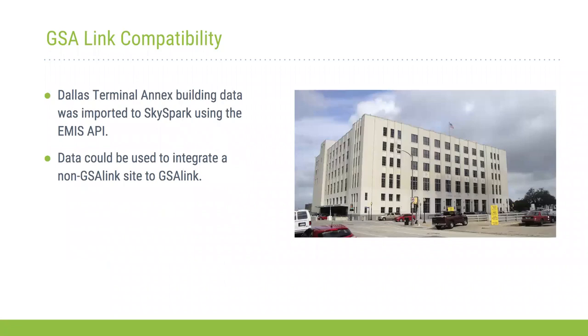Everything was successfully integrated into the product, including BACnet, IP, Modbus - you name it, it's integratable to this, or at least for this project, the ones we tried were. The GSA Link compatibility - we didn't have to modify the API at all, and we just had a successful link to GSA Link. We were able to prove this at the Dallas Terminal Annex building and import data from the software into GSA Link or SkySpark, which was shown on the last slide. Those are just two quick performance objectives, successful connections there.